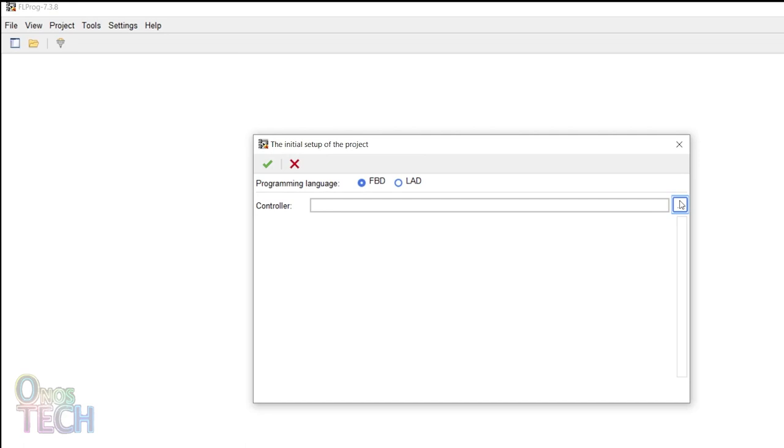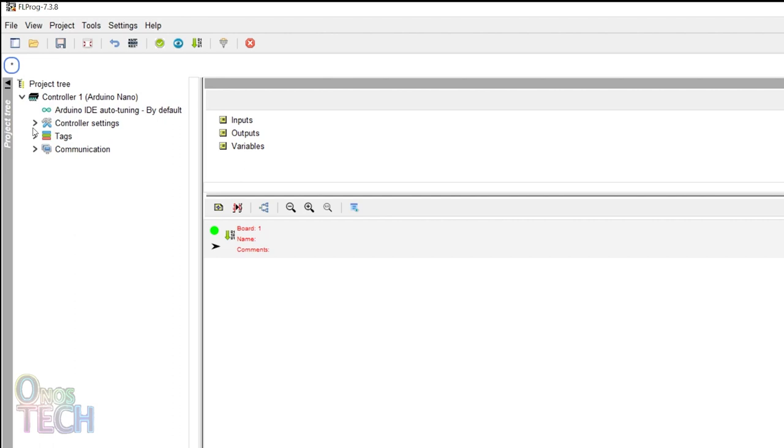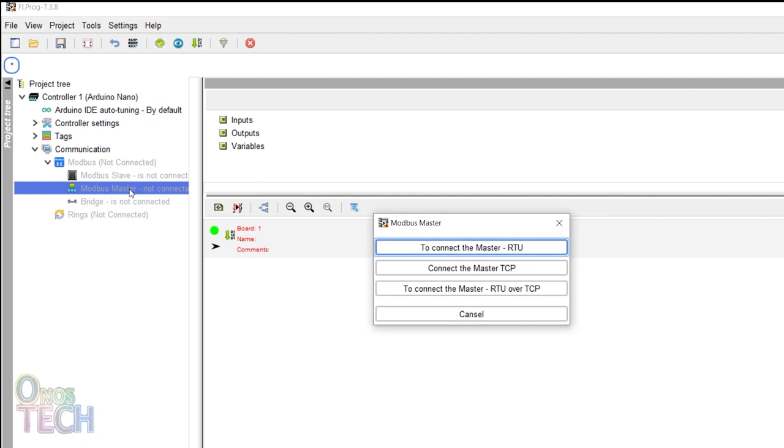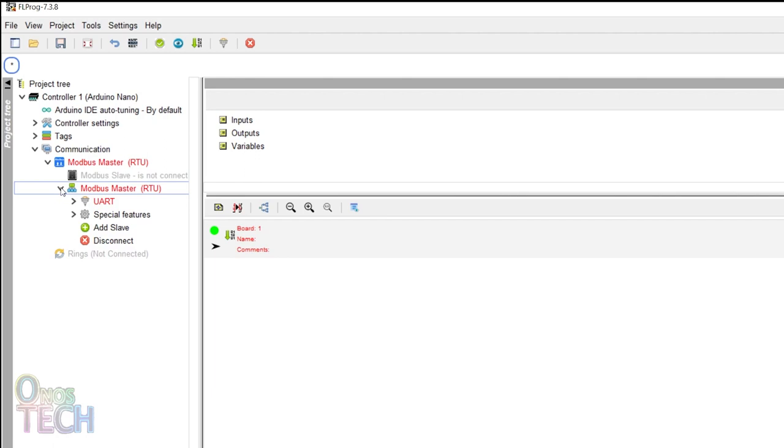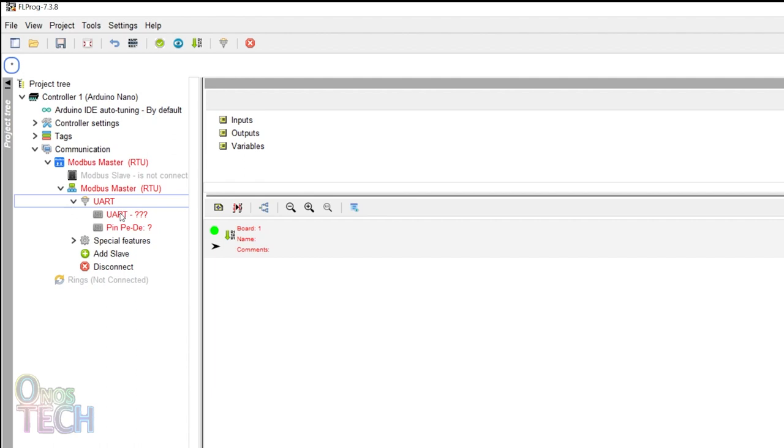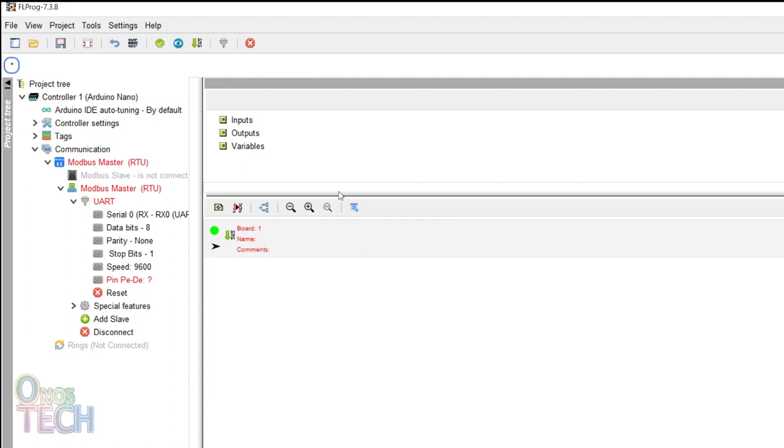Expand the project tree on the left to display the Modbus options. Double-click on Modbus master and select to connect the master RTU. Expand the Modbus master RTU to reveal the UART options and double-click on UART. Select Serial 0 and click OK. I will maintain the UART speed of 9600. Double-click on parity and select No.